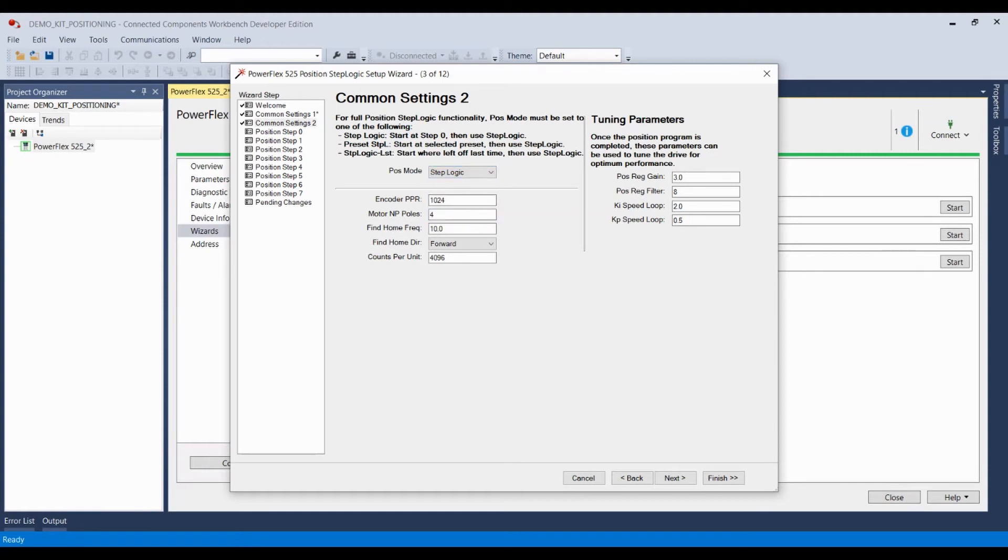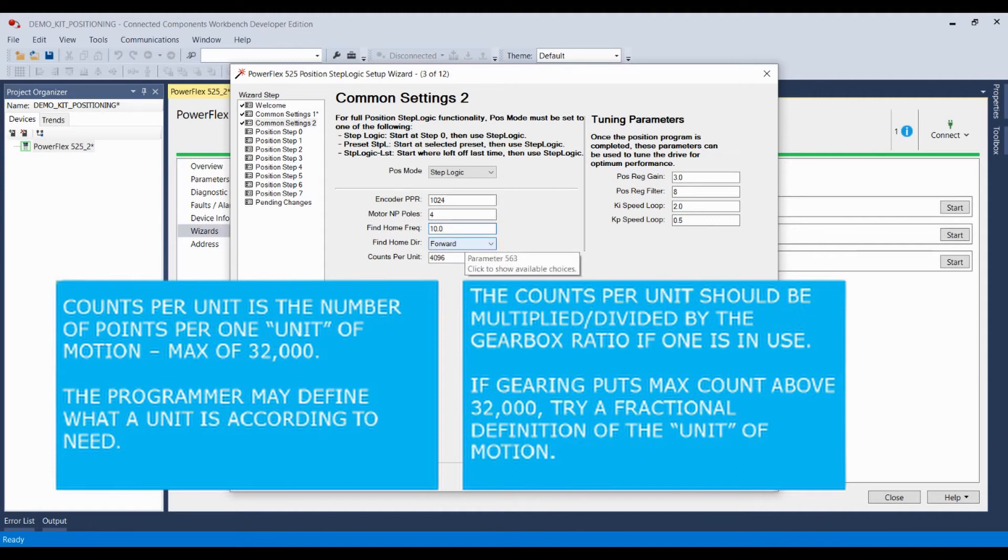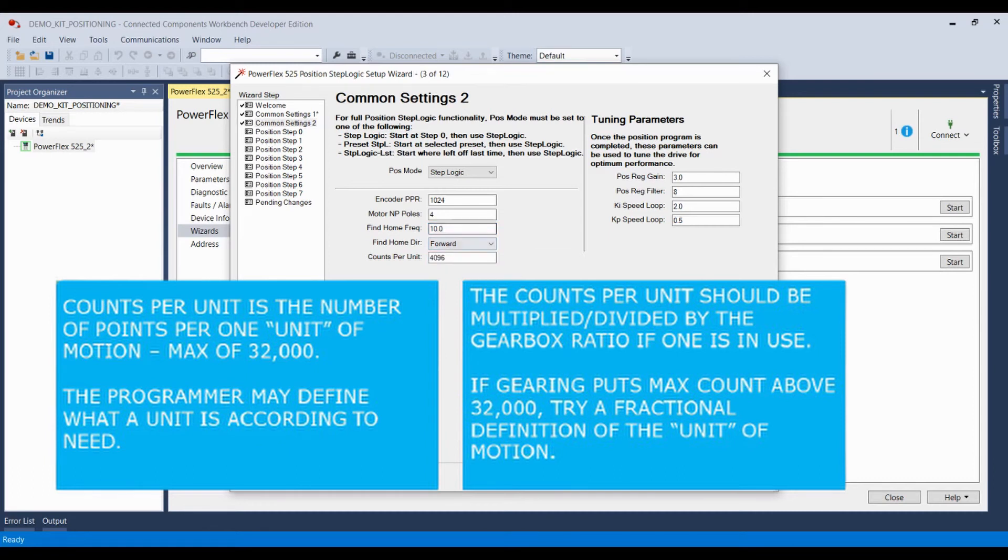You can also install your encoder information. I happen to have a 1024 encoder. My motor is a four pole motor and my counts per unit are 4096. Now the find home frequency is simply the frequency the drive will operate at when it's a find home operation. In this case, 10 Hertz. And the find home direction will be defined as forward. You could make this reverse or whatever is required.